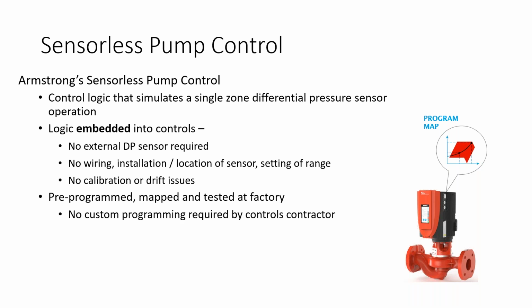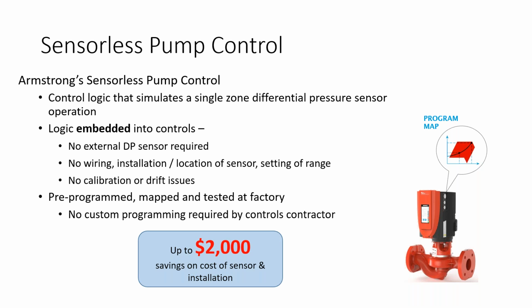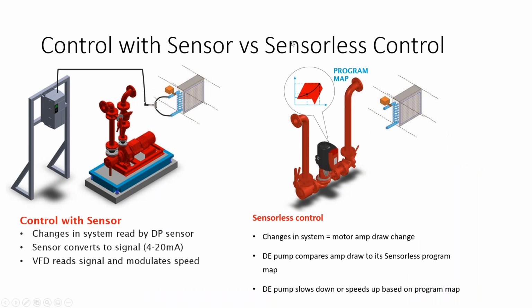All of the logic is embedded on the control. There are no external sensors, no wiring installation, location, or setting of ranges. There's also no calibration, drift, or issues that come up with valves and things like that that we don't know about. It's pre-programmed, mapped, and certified tested at the factory. So there's no custom programming required by a controls contractor. Big plus. That's up to a $2,000 savings just based on eliminating the cost of a sensor installation. So now the control with a sensorless versus a sensored system: basically with the sensor upstream, the changes in the system are read by a differential pressure sensor, and it converts the signal to 4 to 20 milliamps.